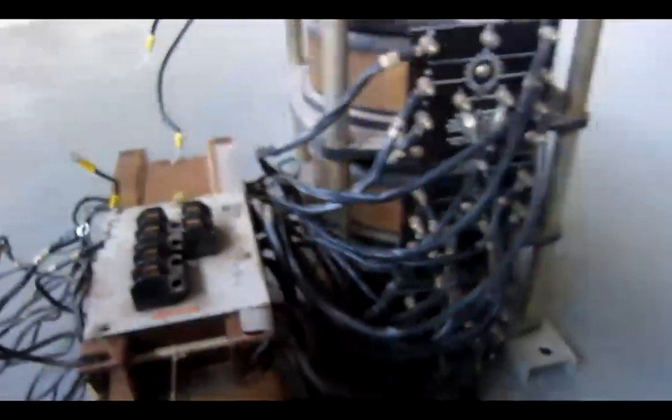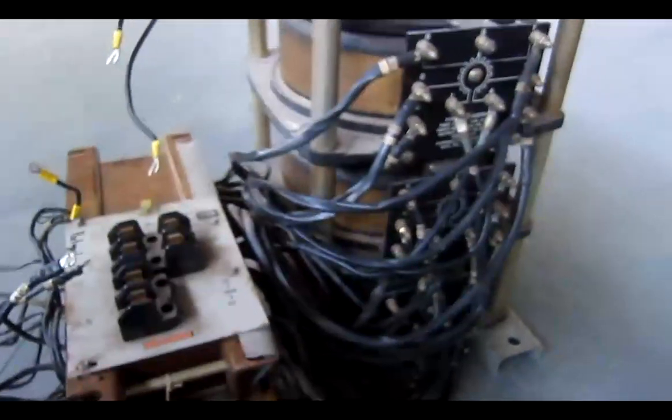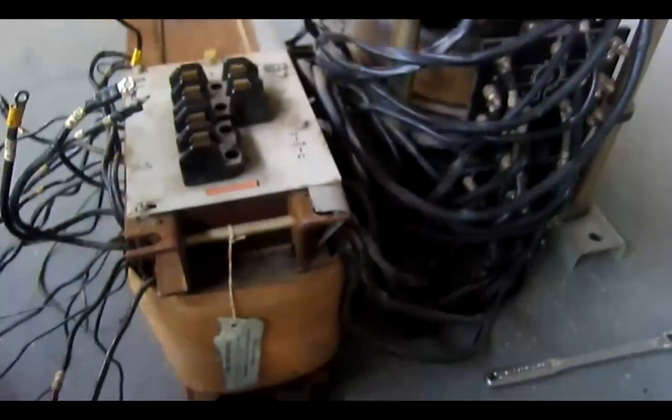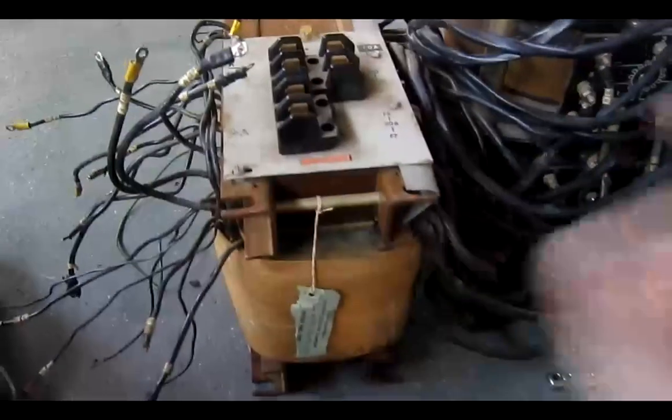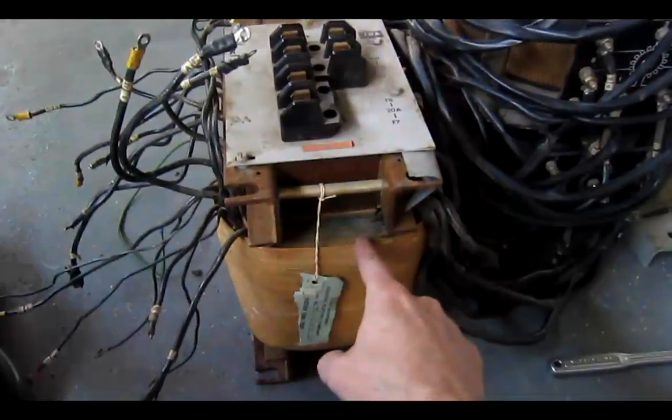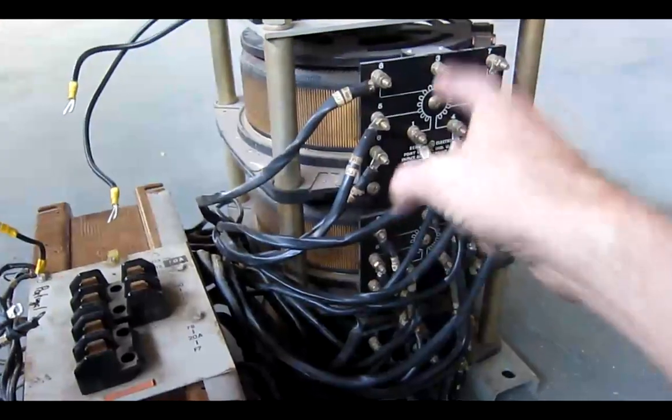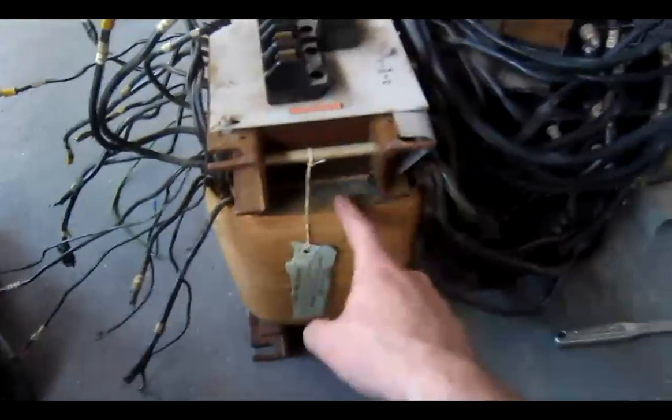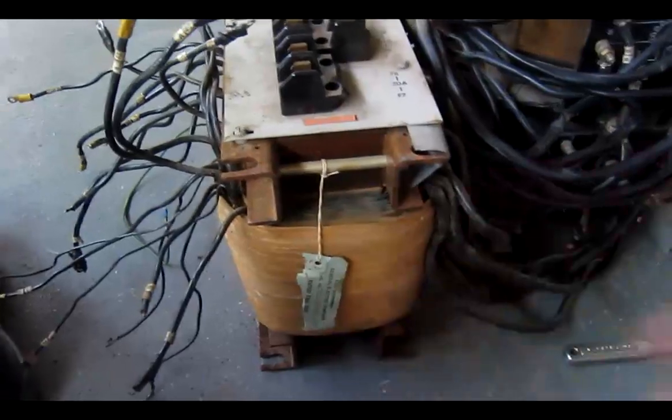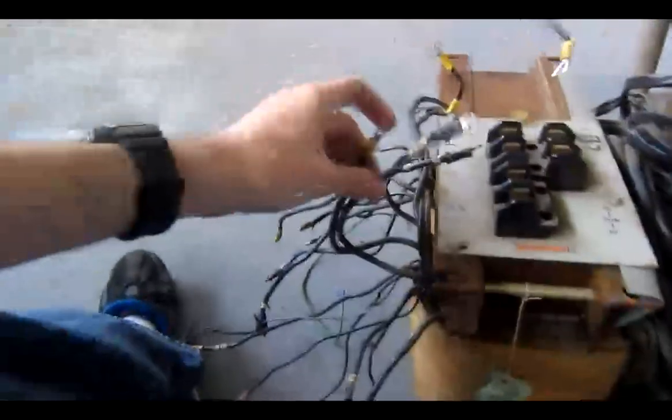We know that because we took it out of service. So I'm hoping somebody out there, one of my viewers, might be able to offer some insight into this so that we can hook it up properly. What I need to know is exactly what this is because I know these are a three-phase variac system rated for 30 amps. I need to know exactly what this is. I'm pretty sure it's inductive current limiting.